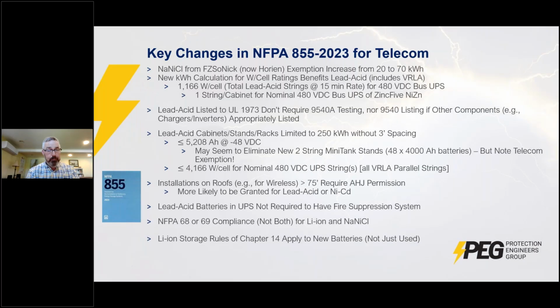One change that was made for the 2023 code is for sodium nickel chloride batteries. They were made by FZSoNick and now Horien. They had an exemption increase from 20 to 70 kilowatt hours. So the code, the standard, I should say, 855, has a threshold of limits of when it applies, how large of a battery or an ESS system can be before the standard applies to it.